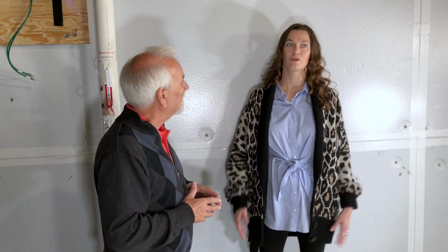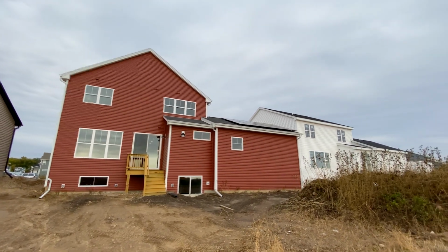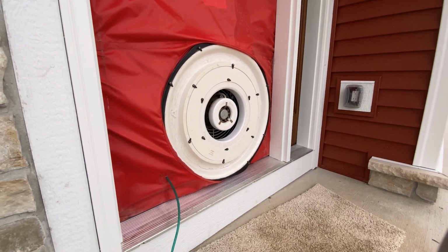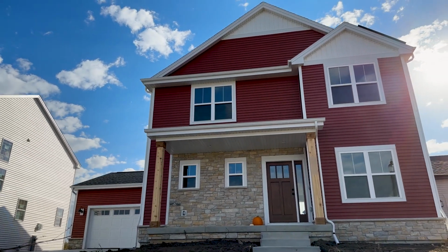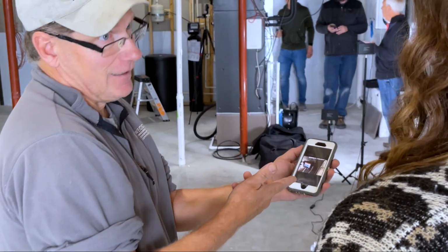So going back to the blower door, what's a good score for that? Well, this is a fair question. What's interesting is there's very seldom two buildings exactly the same physical size, but we can estimate a number up front for a target. For instance, Tim O'Brien Homes likes to shoot for 1.5 air changes at 50 pascals as a goal. When you convert that to natural leakage, when our equipment is gone and the weather is just impacting the building, that's very, very tight. But when you're anywhere near close to that, the software will easily show there's not much of an impact on energy. I would say that with the work we've seen so far, we're probably going to be better than that. But we'll look for that.